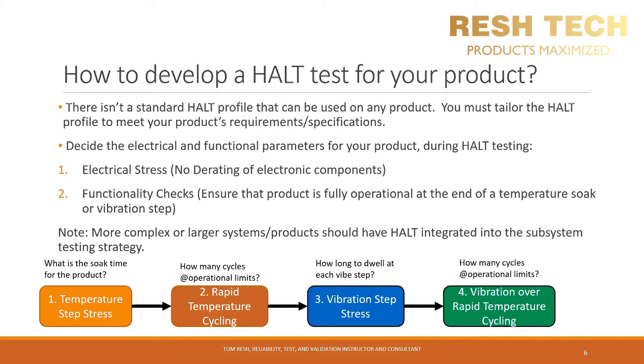Option two is to have a functional test only, to ensure that the device is fully operational at the end of a soak or vibration stress step. You should include a functional test step in your HALT program regardless of whether you perform an electrical stress test in combination with the HALT temperature test — this is to detect abnormalities that indicate when you have reached your product's operational and failure limits. At a minimum, power on your product and have it run in an idle state, along with performing a functionality check to confirm all functions are still operational at the end of each temperature and vibration step. More complex or larger systems should have HALT integrated into the subsystem testing strategy rather than at the full system level.